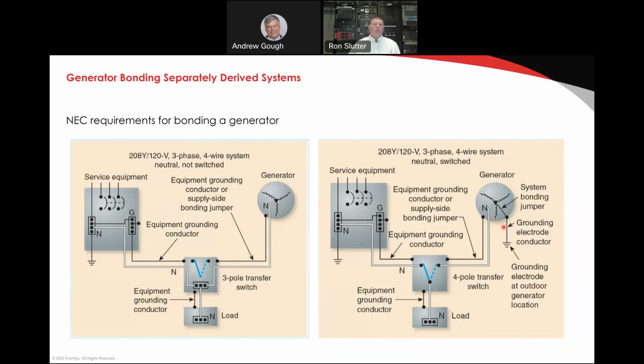When we have to use a 4-pole ATS, notice the difference between these two ATSs that are shown. So this is a solidly connected neutral. On this side, we see that the neutral is switched. And when we switch the neutral, now this is larger critical facilities, right? But these are the sites that matter when we get into these kinds of environments. Notice that when we have a 4-pole ATS, then the generator has to be bonded. So we have a bond in the service equipment, and we have a bond in the generator.